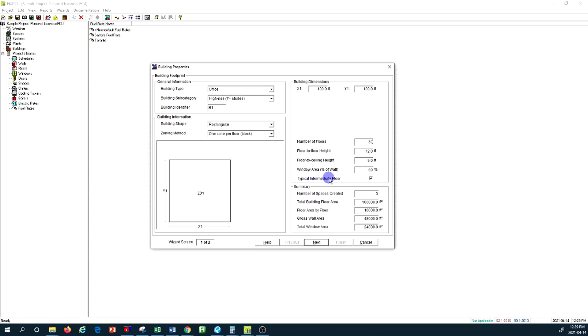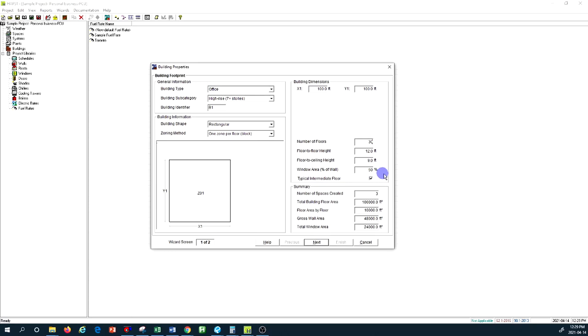Average window per ratio to wall I'm going to keep at 50%, meaning that 50% of our entire building envelope surface would be windows. I'm going to keep it as is. And for here this is important: typical intermediate floor. So if we keep this checkmarked, basically the report that we get is based on the difference in the load in each level.